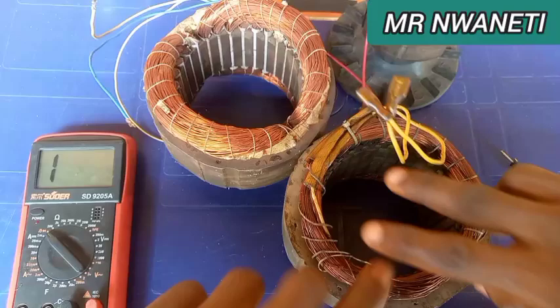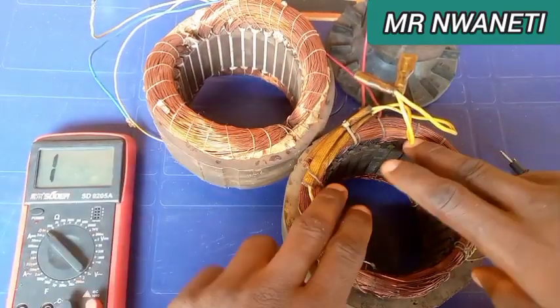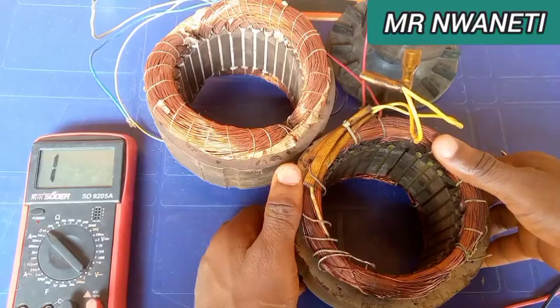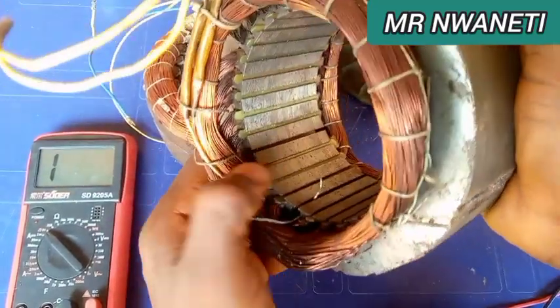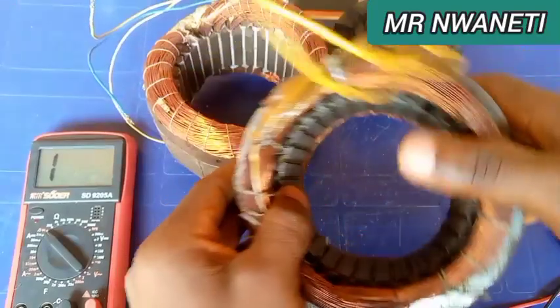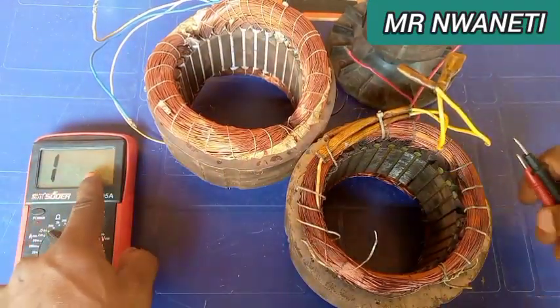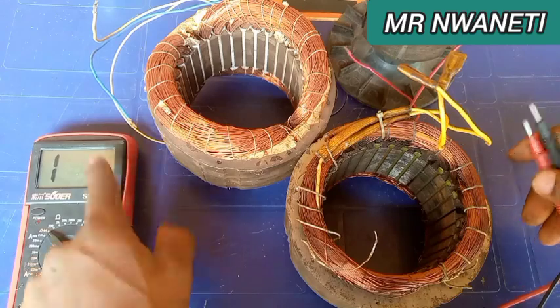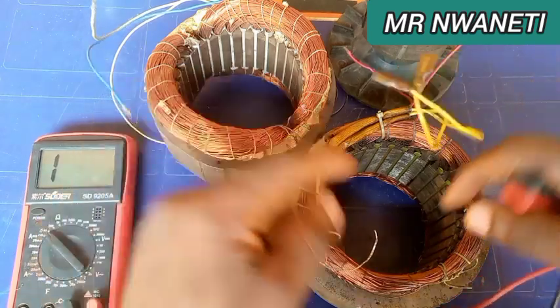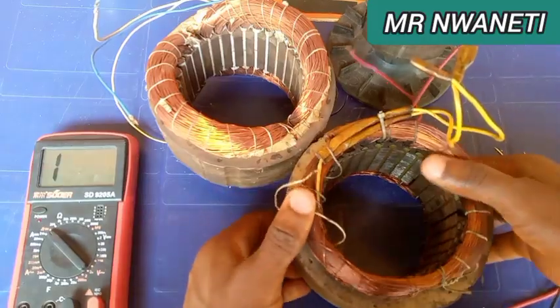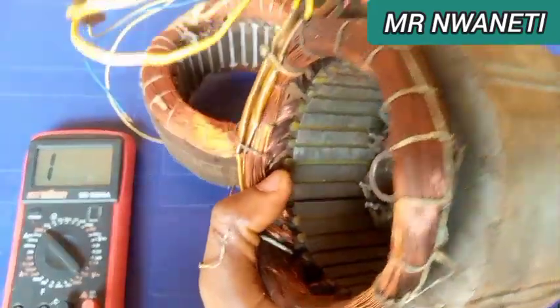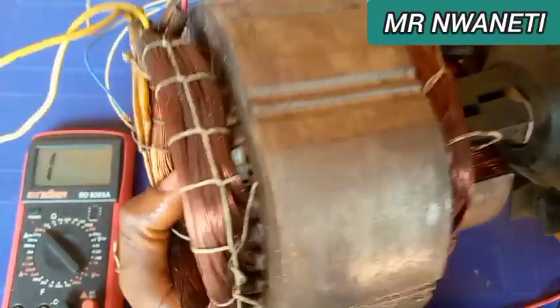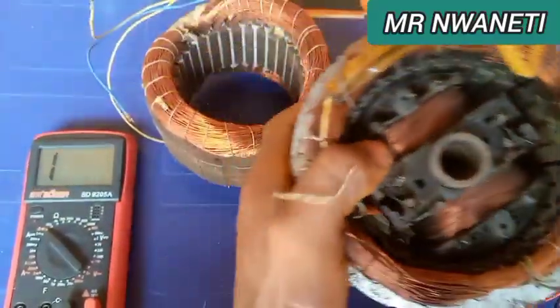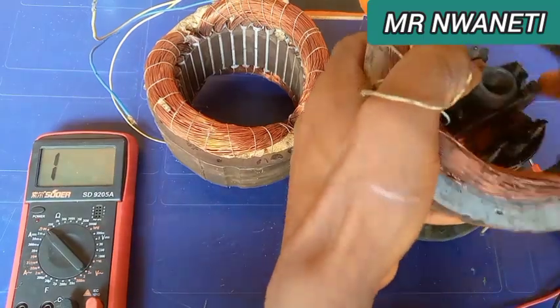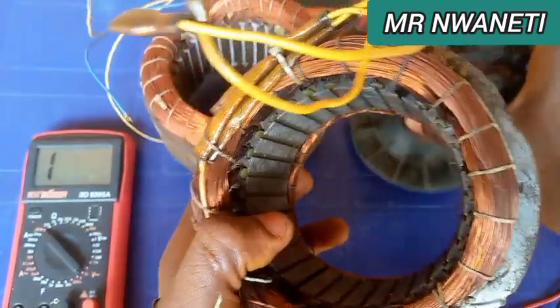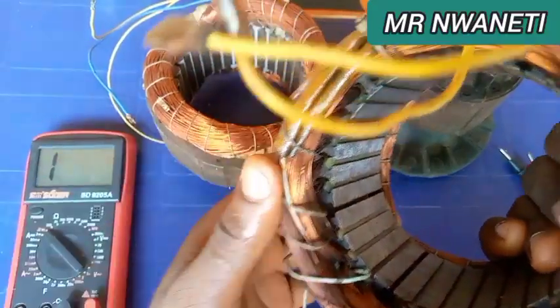Assuming you want to increase the voltage, if you add more turns on this exciter winding, say you increase it from 8 ohms to 10 ohms, the voltage will increase, because when the armature rotates, it is the exciter turns that determine the magnetic strength.